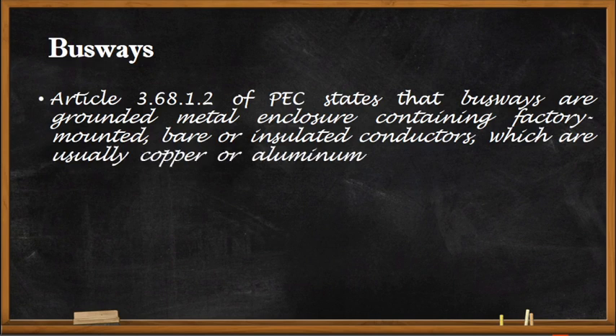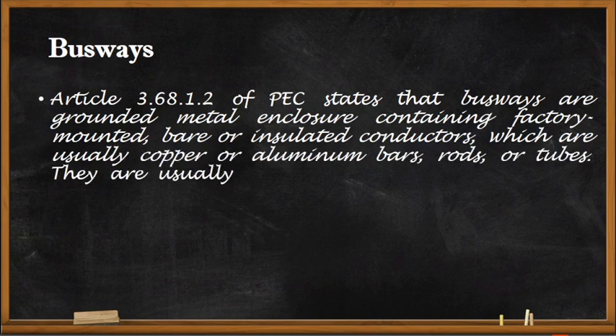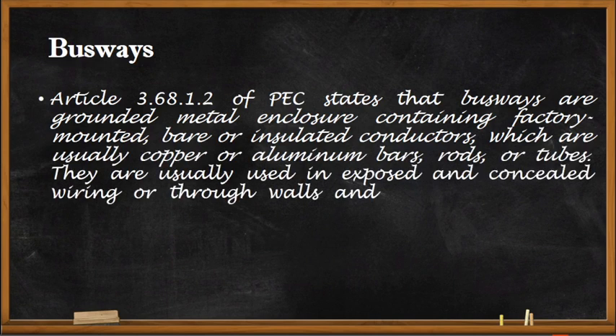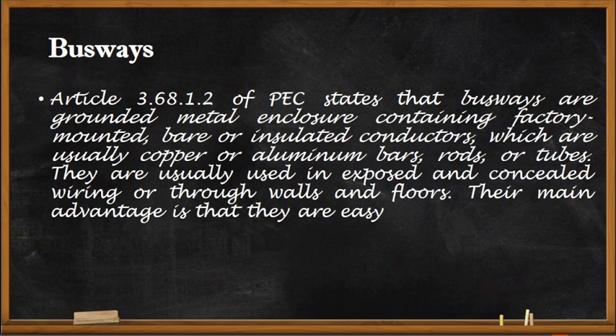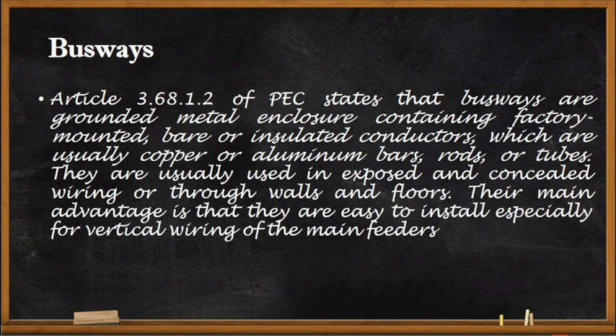The first type is a busway. Article 3.68.1.2 of the Philippine Electrical Code states that busways are grounded metal enclosures containing factory-mounted bare or insulated conductors, which are usually copper or aluminum bars, rods, or tubes. They are usually used in exposed and concealed wiring, or through walls and floors.